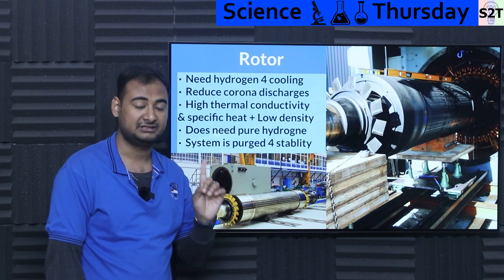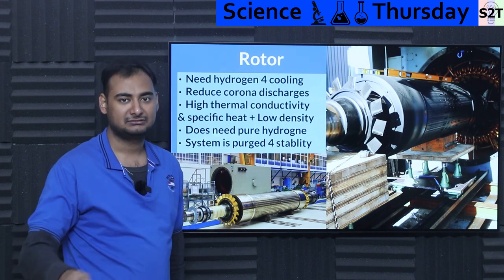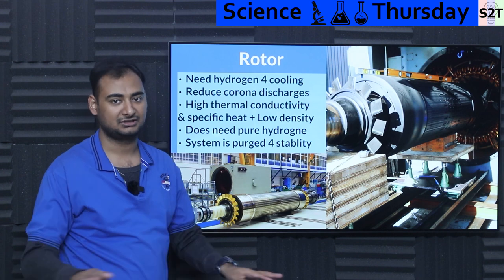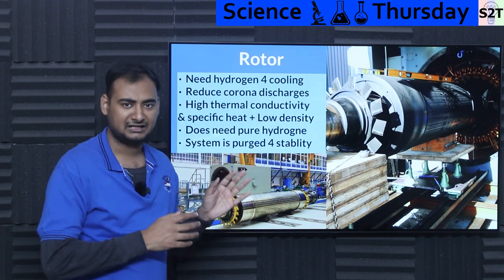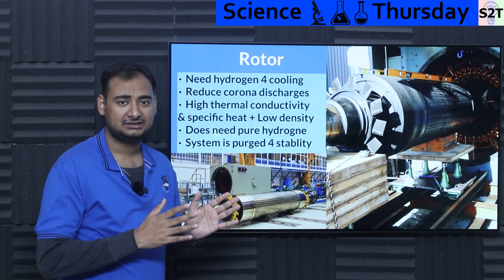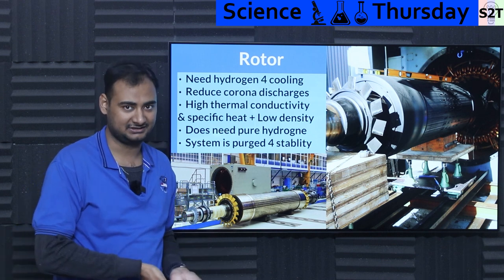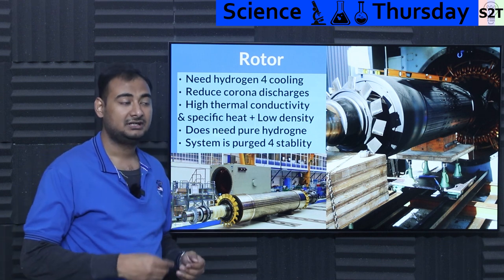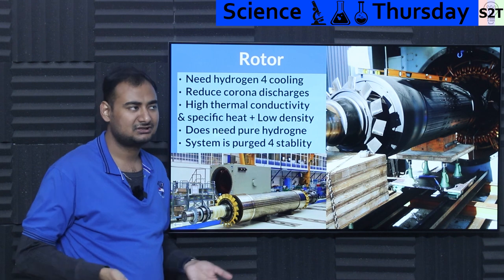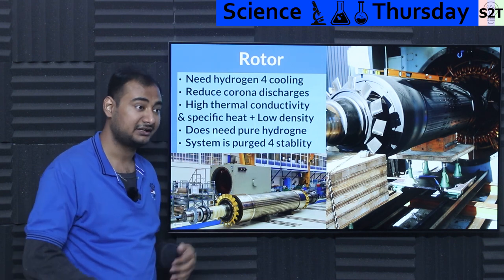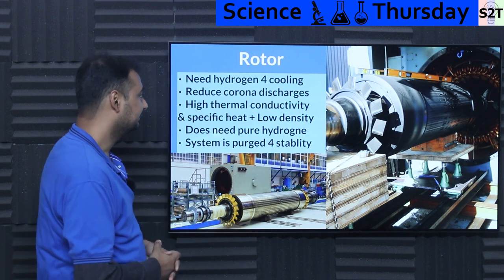Anytime the generator detects purity is not high enough, it will first trigger alarms. If nobody rectifies the situation, it will shut the generator down. Does it cause an explosion? Rarely — because inside the chamber it's close to 100% hydrogen, so there's not enough oxygen to combust. Outside, as long as concentration is below 4%, it won't ignite. Venting procedures are in place to prevent accidental explosions. That's how the rotor is protected.